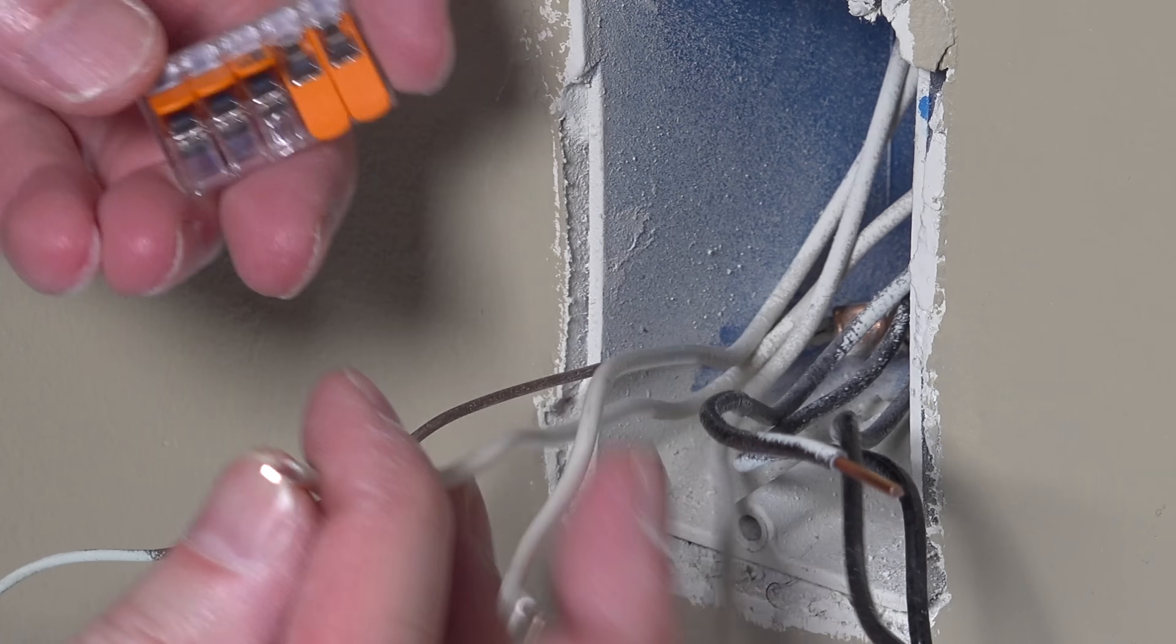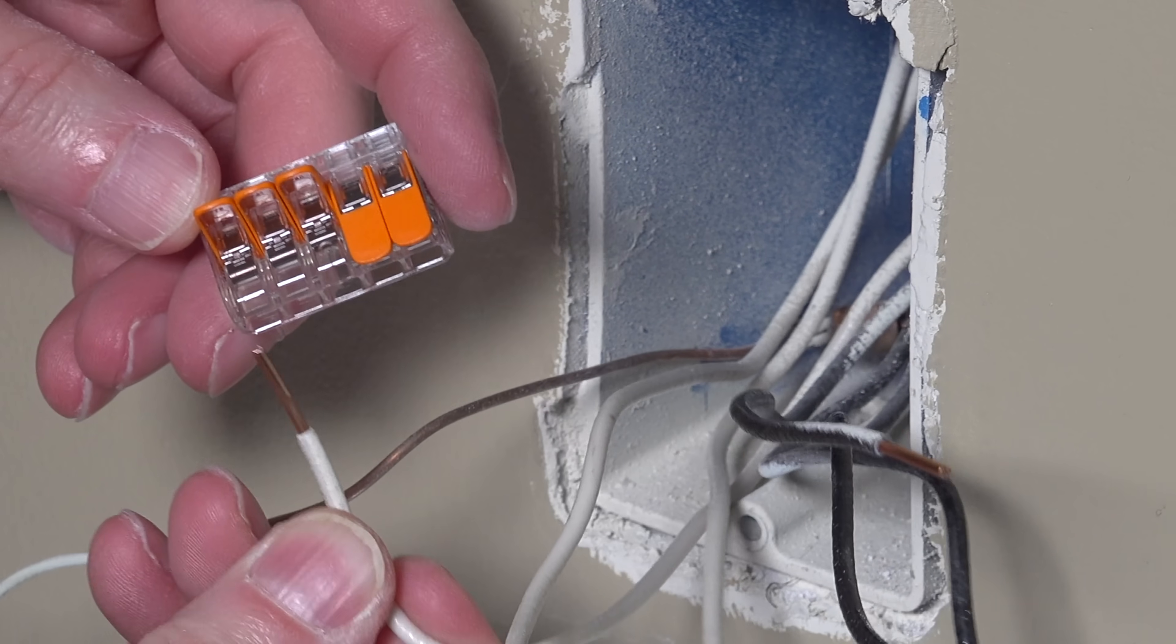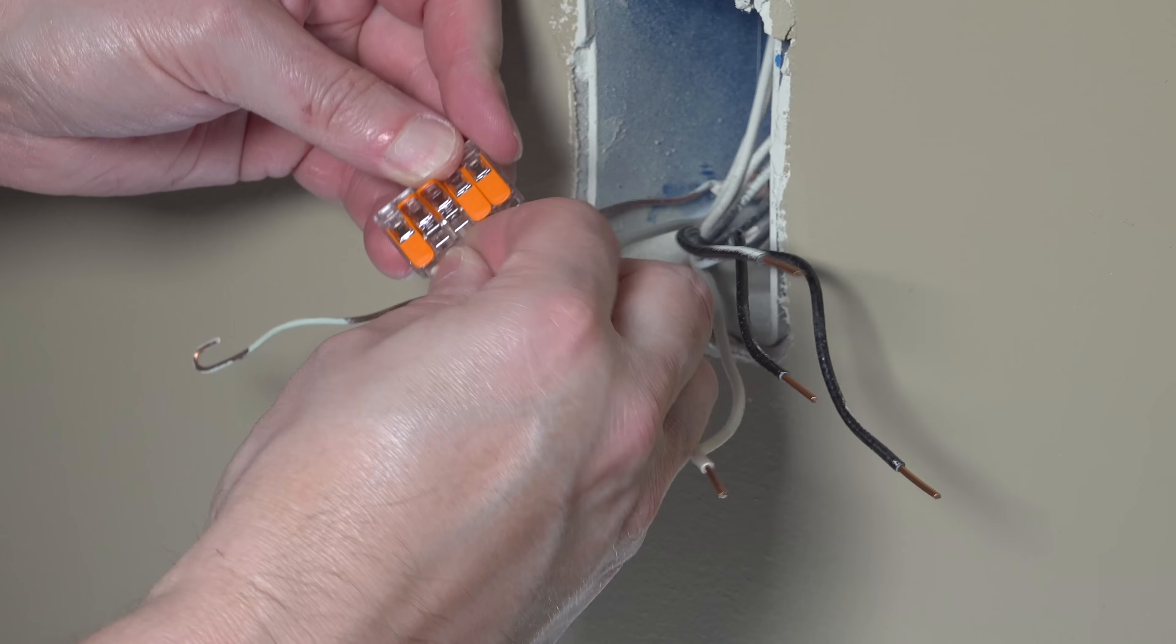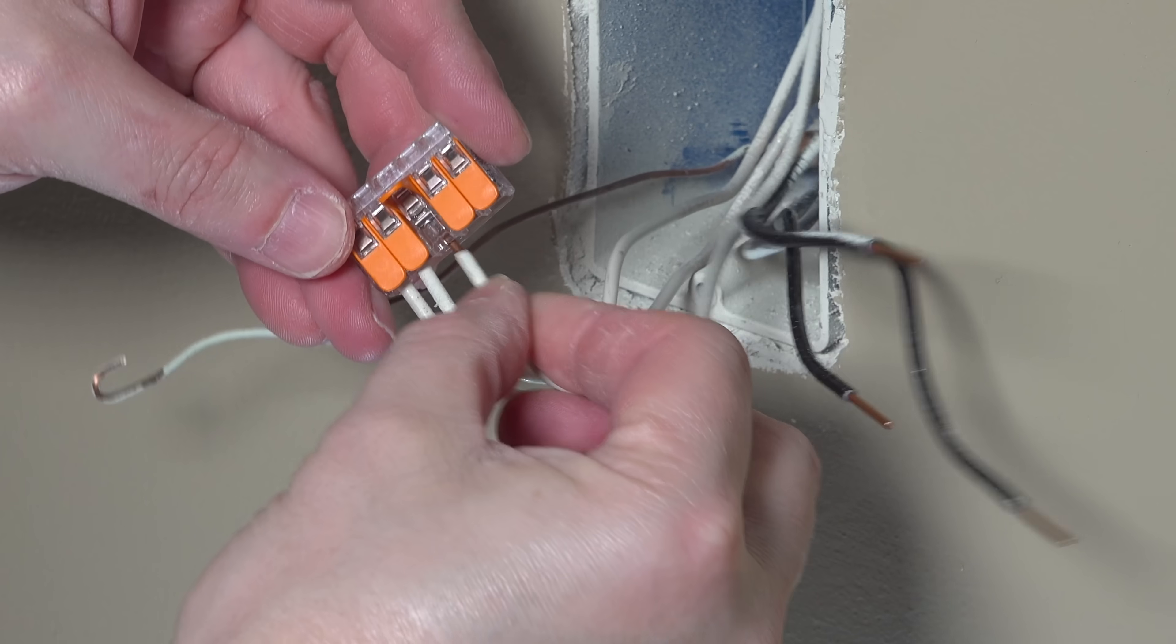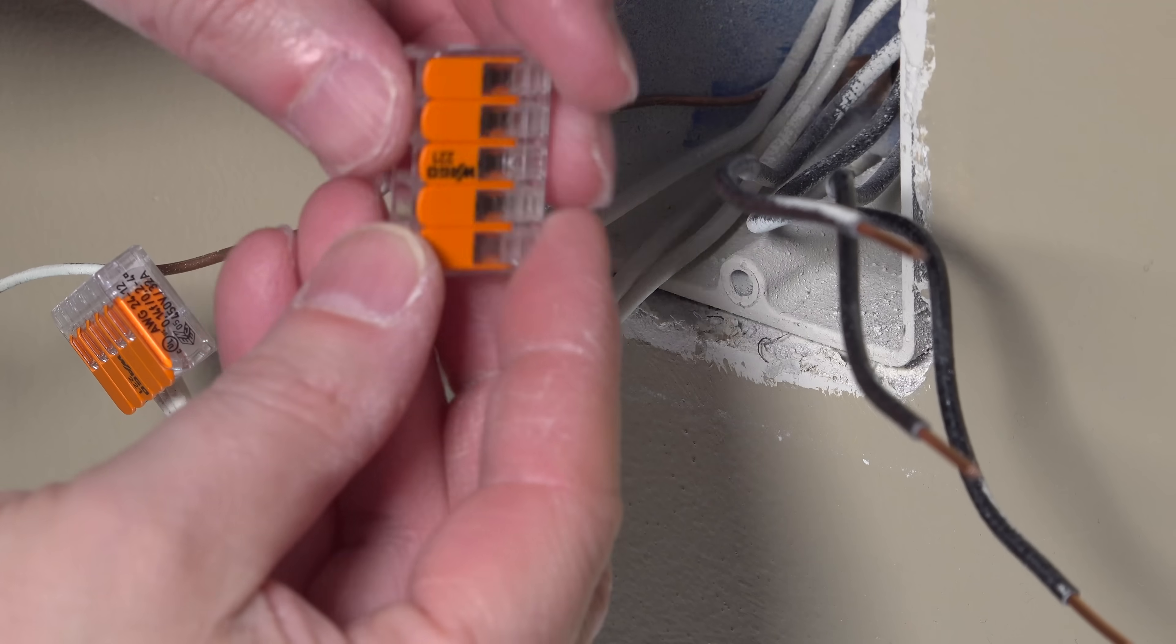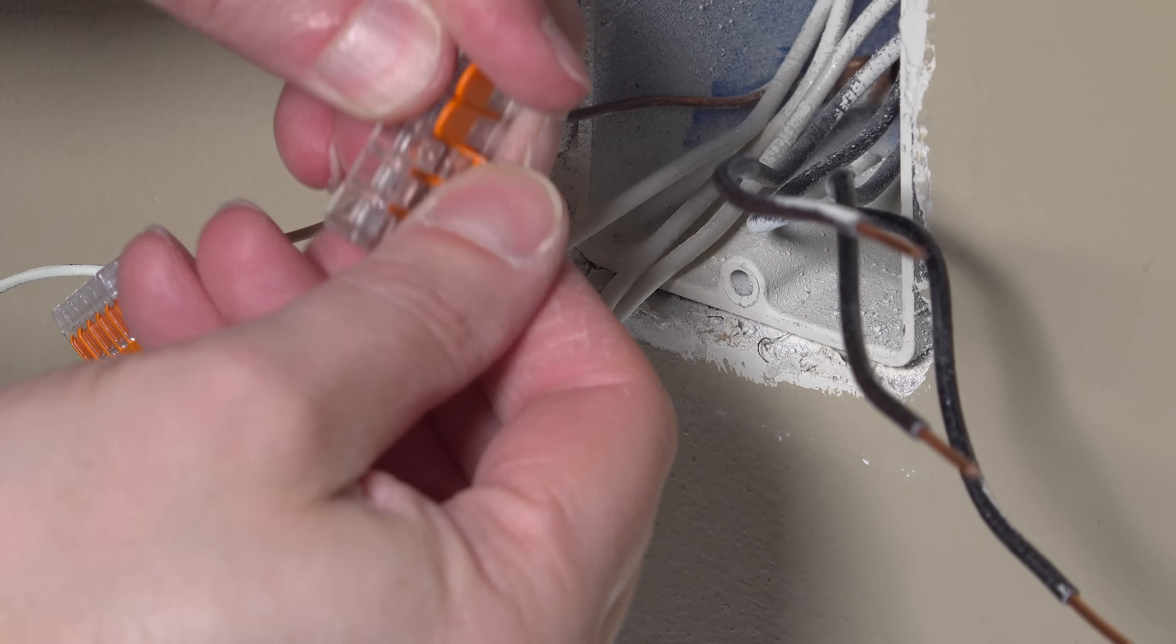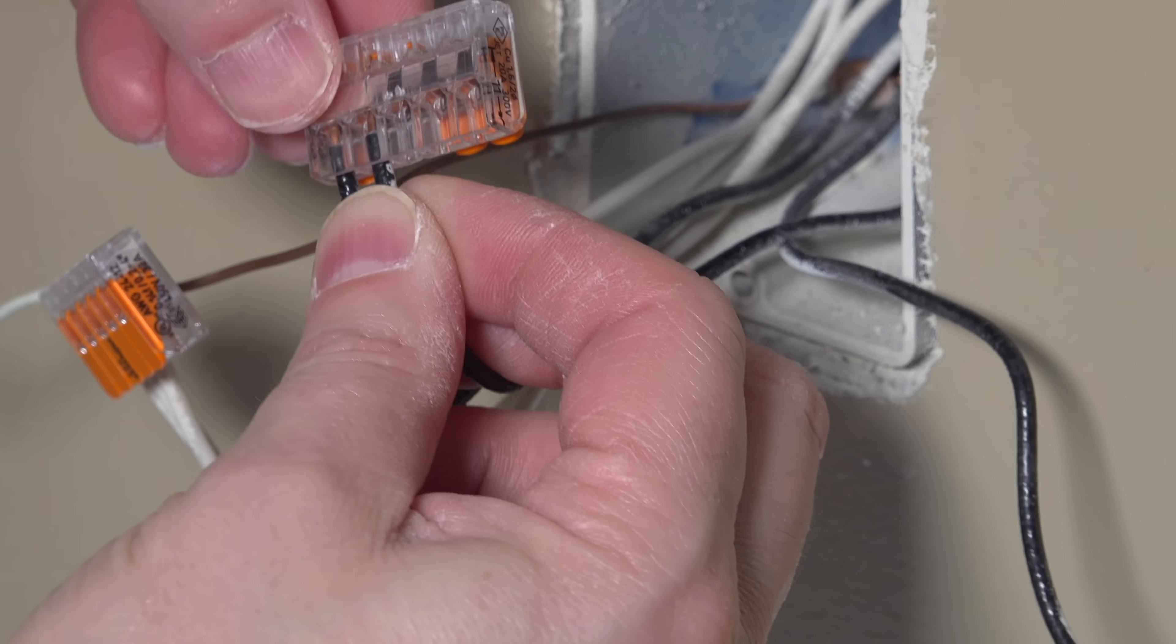Now to do that, you just flip up each lever and insert the wire in as far as it'll go, and then just flip the lever down. If you make a mistake, you can flip the lever back up and remove it. The other great thing about these WAGOs is that they're clear and you can see that the wire is actually inserted in all the way and correctly.